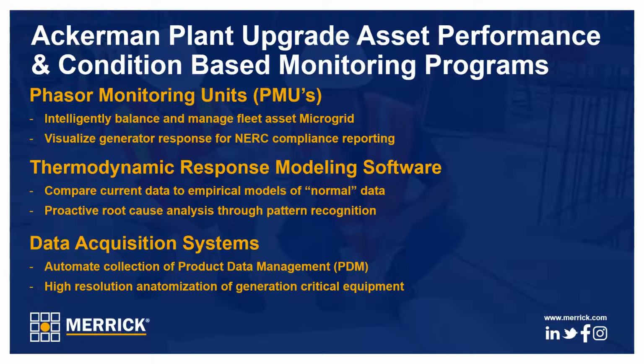The other project Merrick implemented at Ackerman was a data acquisition system, or DAS, to automate the collection of critical asset data. The DAS provides a high-resolution anatomization of key equipment data. In this case, boiler feed water and cooling pumps loading and vibration, generator step-up transformer thermal imaging, and turbine vibration signals were collected for analysis.